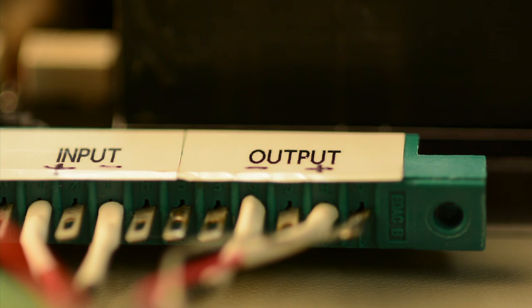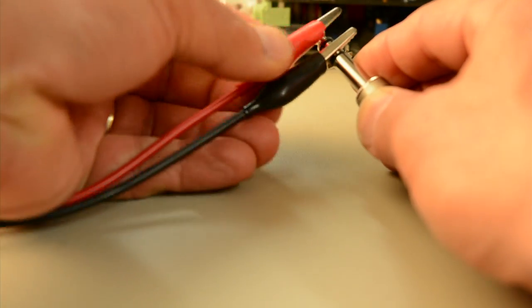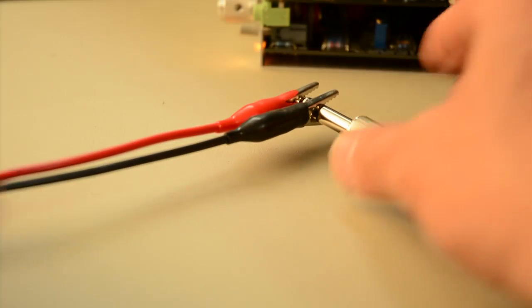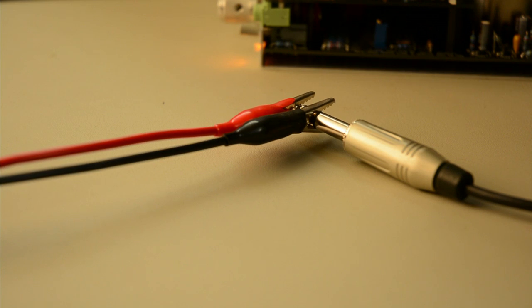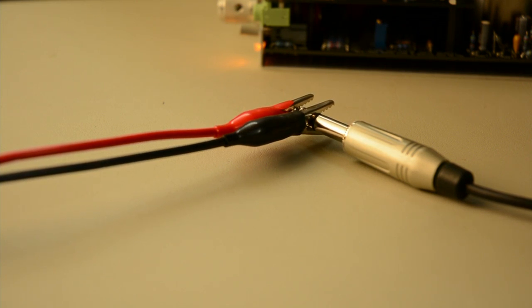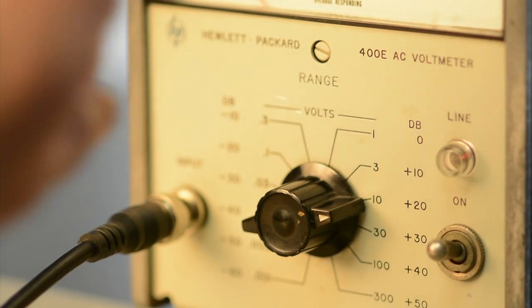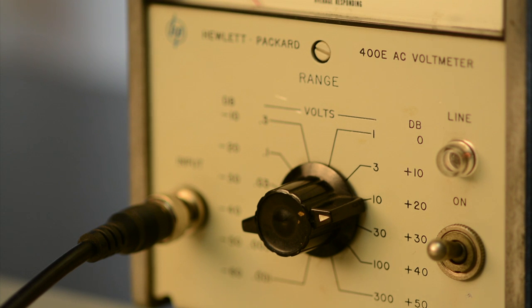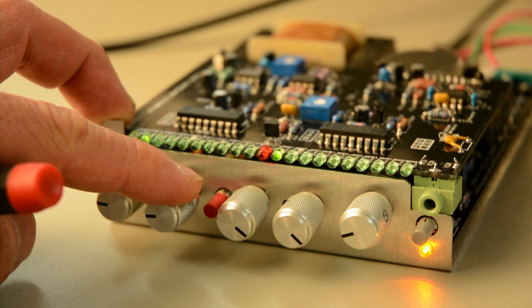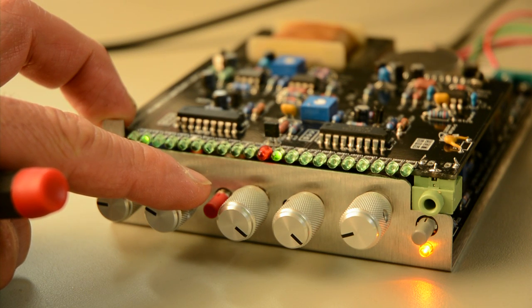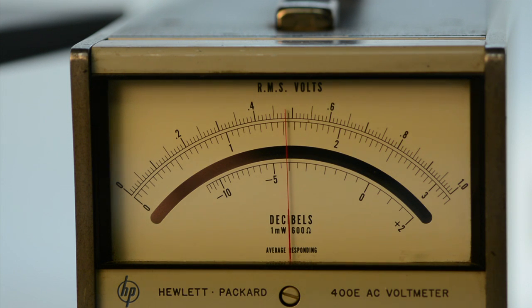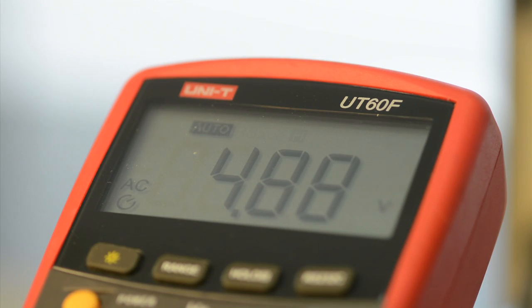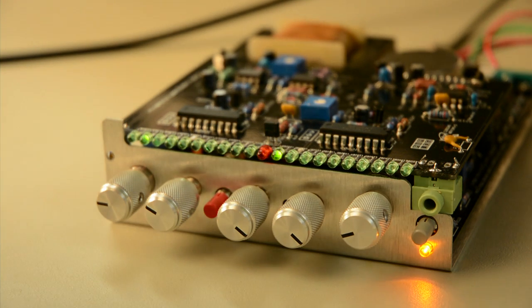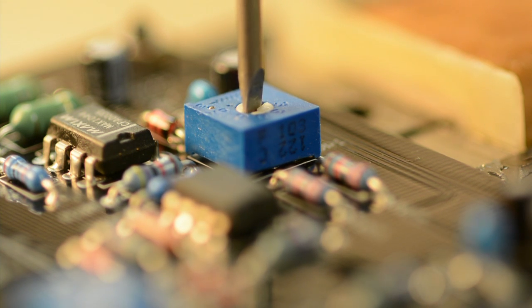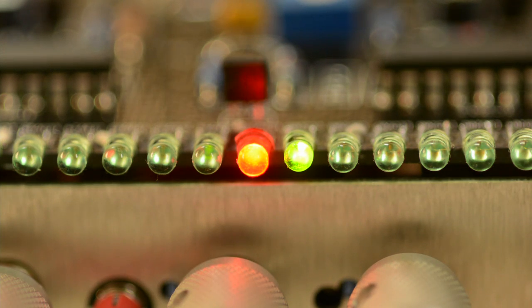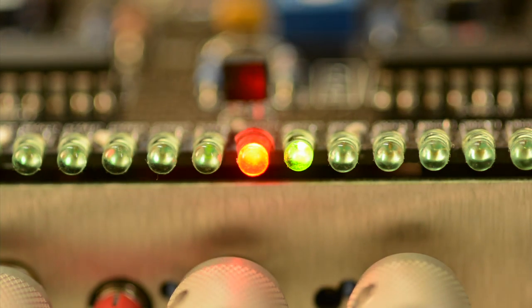Now connect your AC voltmeter to the output terminals 2 and 4 of the 500 rack. Do not connect the voltmeter to the FET500's ground. Set your AC voltmeter to measure in the 10 volt range. Increase the output control until the output level reaches 16 dBu or 4.88 volts RMS. Adjust VR1 on the meter board until the peak indicator LED just lights. This sets the peak LED threshold.